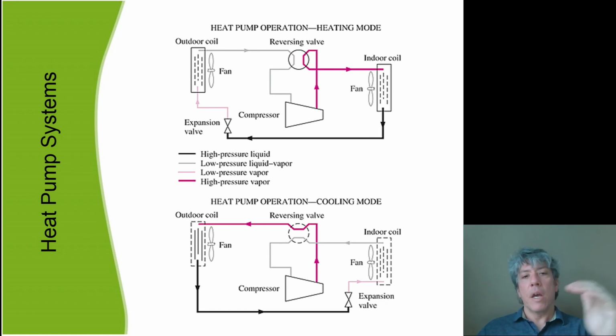It's a superheated gas. So it goes through the outdoor coil, and it is cooled. All right, so its temperature drops, but it drops to a point where it starts to liquefy out. As a matter of fact, there's a trap on the end of the outdoor coil to prevent anything but liquid from going on through that black arrow. So that black arrow is all saturated liquid that is still at a relatively high temperature and pressure, but it's lost a lot of energy because it went from a vapor to a liquid.